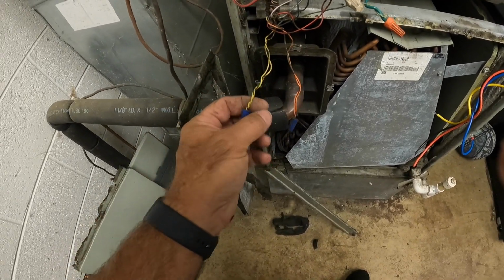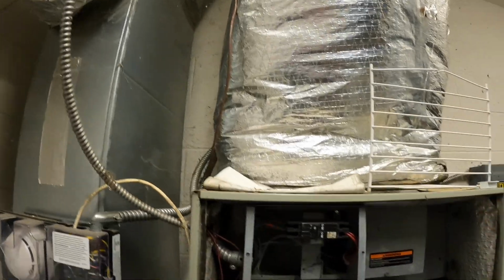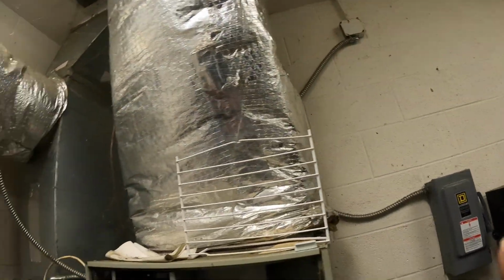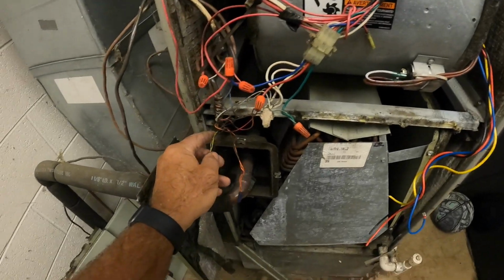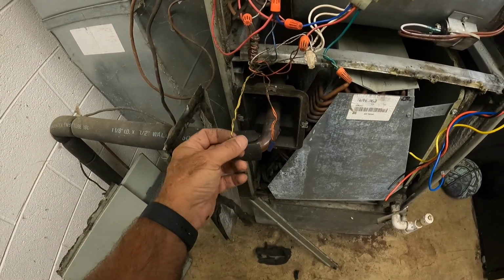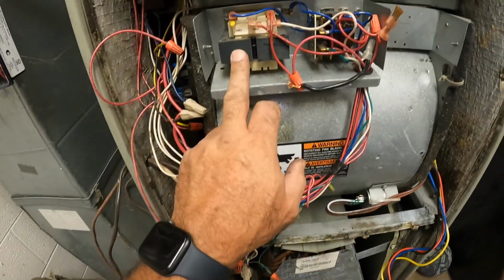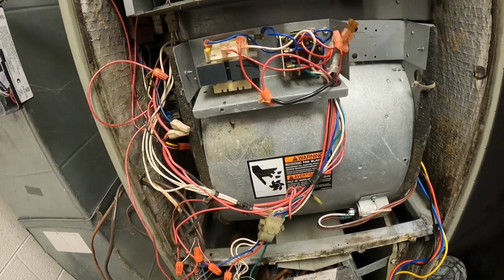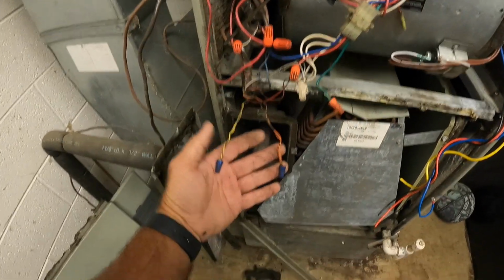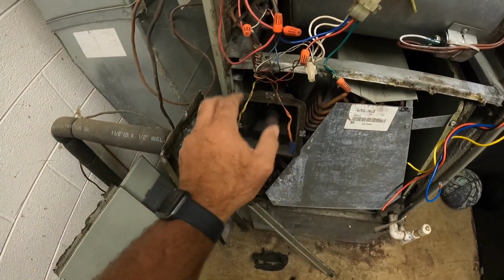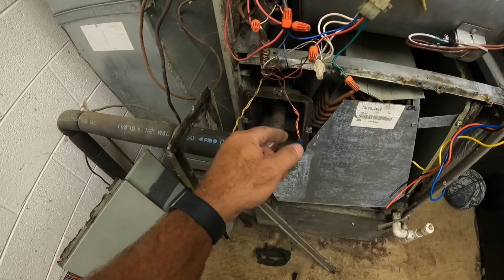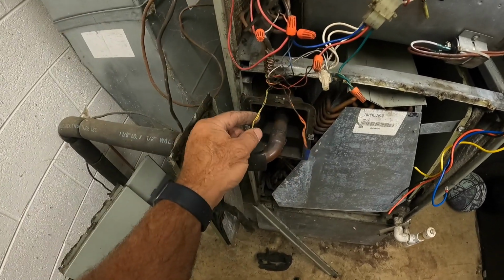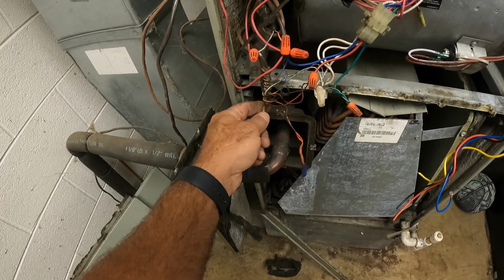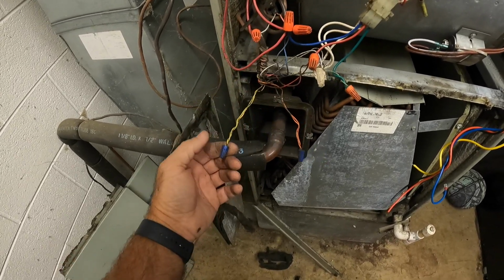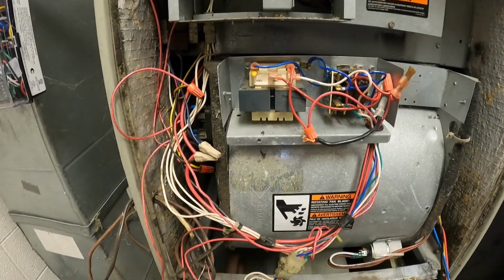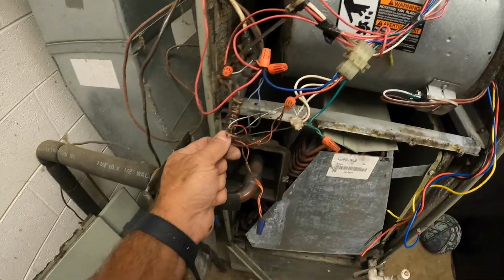These building control systems, they've got a unitary controller probably over inside the actual offices, and it can either be powered up by the transformer in the unit, or some of them they put separate transformers on them, and then it just uses dry contacts to switch the stuff on and off coming from the unit. You know, it would send our red back there, and then it would send it back out on the yellow. So I'm not sure which this is, but either way there shouldn't be any voltage on these wires once we turn our transformer off, which we've done. So I can go ahead and unhook this safely.